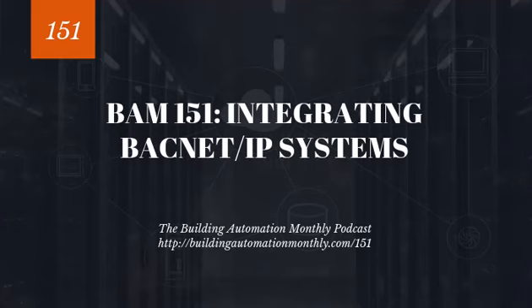And I want you to be honest with yourself and ask, why was it a nightmare? Why was it so hard? I mean, it should have been easy. We've been doing BACnet IP forever, but yet it was hard. Oftentimes what will happen is things fall apart in this data flow map area. That's because we don't look at what points we have. We don't look at what devices we have, and we don't look at what properties and services the points have. Because we're not looking at the services and properties, we don't know what we're writing to, and we don't know what we're reading from, and we don't know at what priority we're writing.